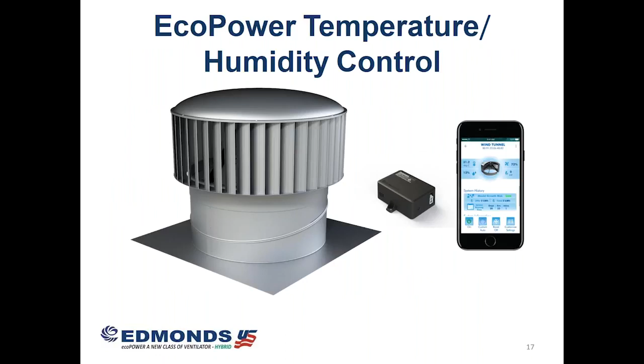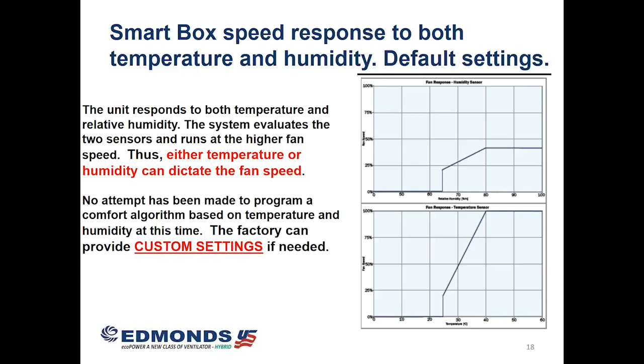The smart box comes with default settings unless the customer has requested preset conditions. Temperature or humidity may be controlling the speed of the ventilator depending upon which variable exceeds its preset minimum first. Humidity default is 65%, while temperature minimum default is 77F when speed rises to 20% of permitted capacity. It then ramps up to full speed at 104 Fahrenheit. But I stress these settings can be reprogrammed to suit various geographic conditions.